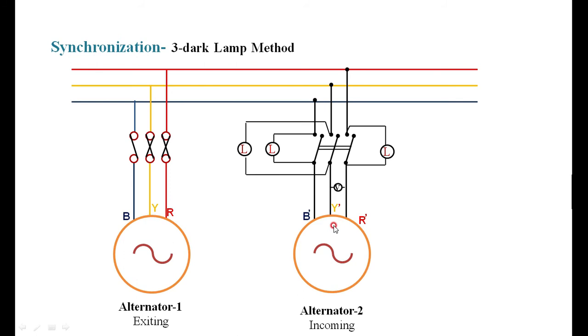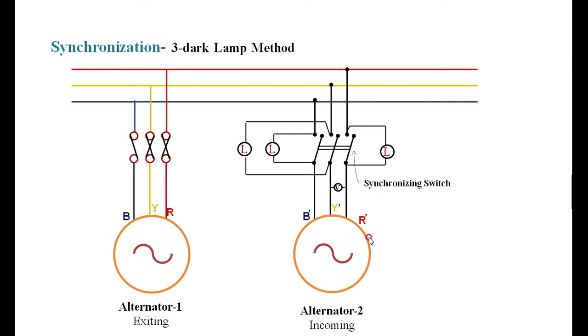The fourth condition is that the phase of the incoming machine must be the same as the bus bar phase. If the phase of the bus bar and the generated voltage are equal and opposite, the voltage across the bulb is zero and the bulb will not glow. Therefore, when you observe the lamp going completely dark, you must close the switch — this switch is called the synchronizing switch.